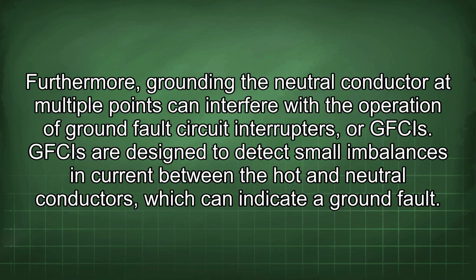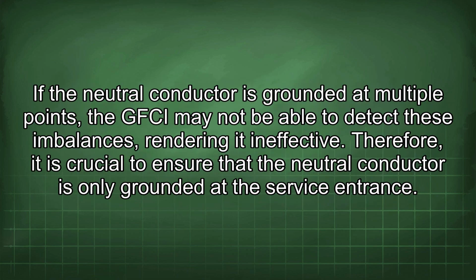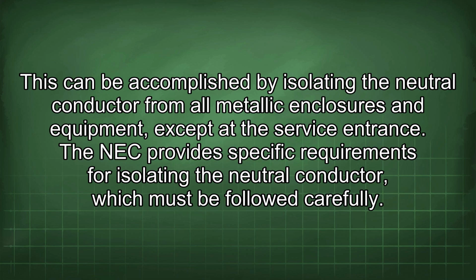Furthermore, grounding the neutral conductor at multiple points can interfere with the operation of ground fault circuit interrupters, or GFCIs. GFCIs are designed to detect small imbalances in current between the hot and neutral conductors, which can indicate a ground fault. If the neutral conductor is grounded at multiple points, the GFCI may not be able to detect these imbalances, rendering it ineffective. Therefore, it is crucial to ensure that the neutral conductor is only grounded at the service entrance. This can be accomplished by isolating the neutral conductor from all metallic enclosures and equipment except at the service entrance. The NEC provides specific requirements for isolating the neutral conductor, which must be followed carefully.